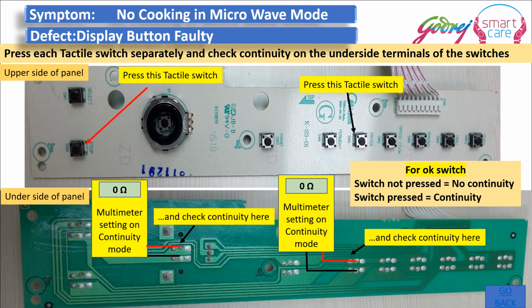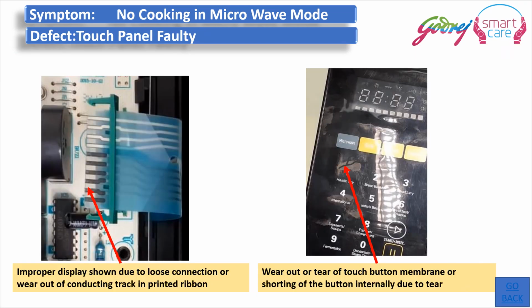Here, for the first defect, if the buttons are faulty and we are not able to operate the machine, we can check the continuity of the buttons by pressing them and checking on the points which are indicated in red and black over here. Across these points there should be continuity when we press the buttons. Each and every button we can check in this way. We can put the multimeter on continuity mode and check the continuity between these red and black points indicated in this diagram. Every individual button can be physically pressed and the continuity checked. This is the way of checking the button.